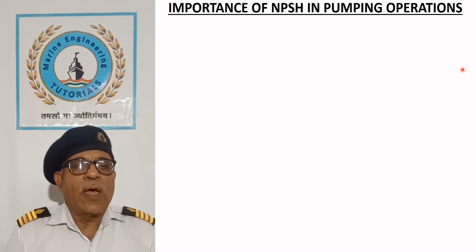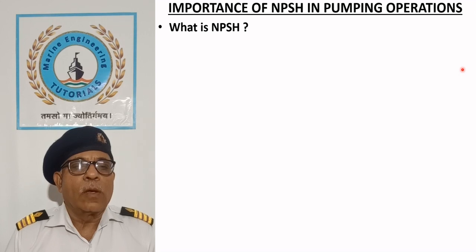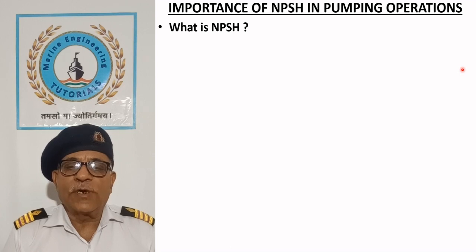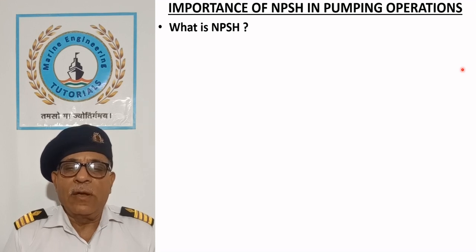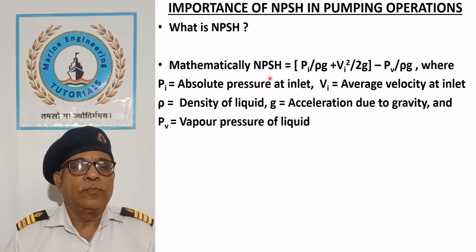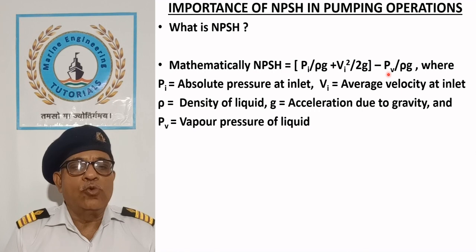Importance of NPSH in Pumping Operations. What is NPSH? NPSH or Net Positive Suction Head is defined as the sum of static and dynamic head minus vapor pressure head. The sum of static and dynamic head is called the suction head. Mathematically, NPSH equals PI by ρg plus V² by 2g minus PV by ρg.